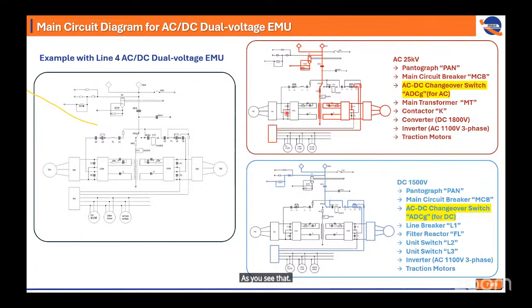As you see here, in the AC section, the AC 25 kV goes to the pantograph and main circuit breaker, and the AC/DC change switch. Then this AC change switch supplies the input power to the main transformer area, which goes to the contactor, then to the converter at DC 1,800 voltage, then to the inverter for the traction motor. In case of DC 1,500 voltage, the pantograph still goes to the MCB first, and also to the AC/DC switch, then directly to the line breaker and filter reactor and to the inverter directly, not through the converter side.